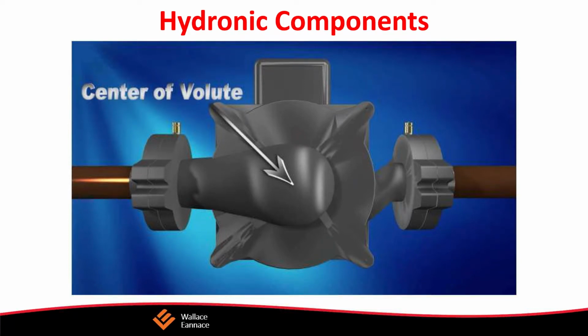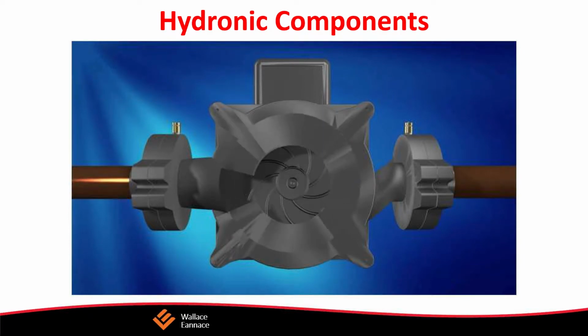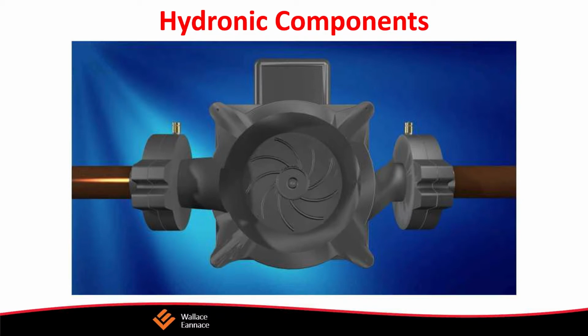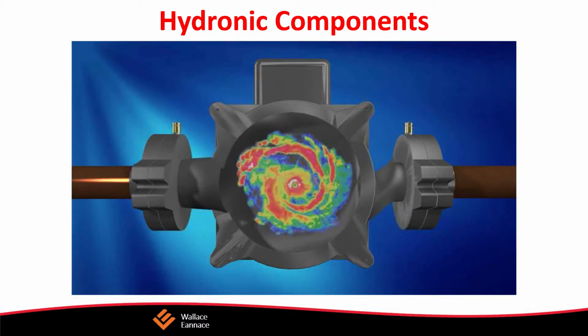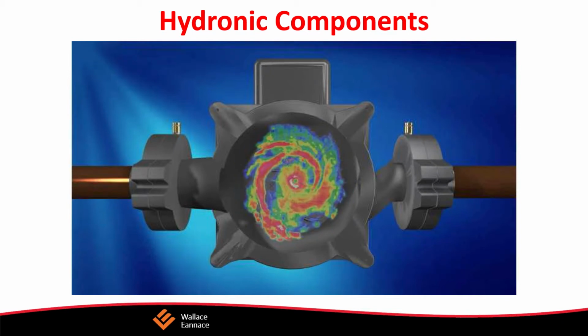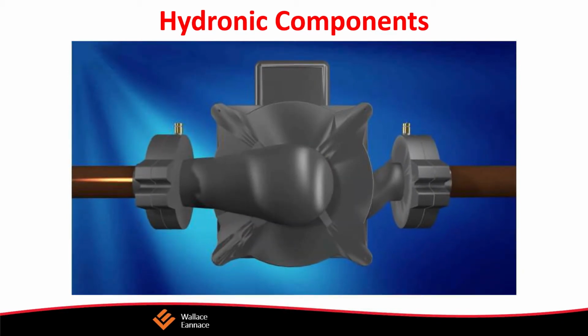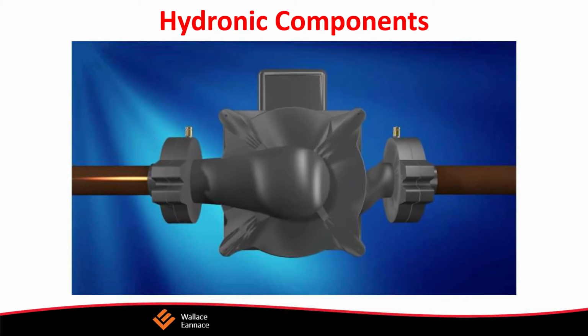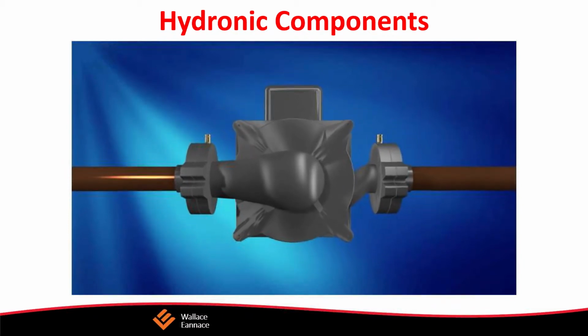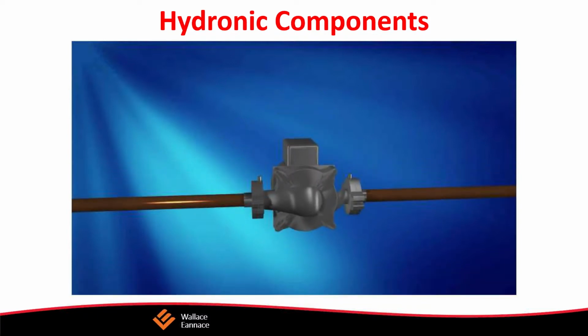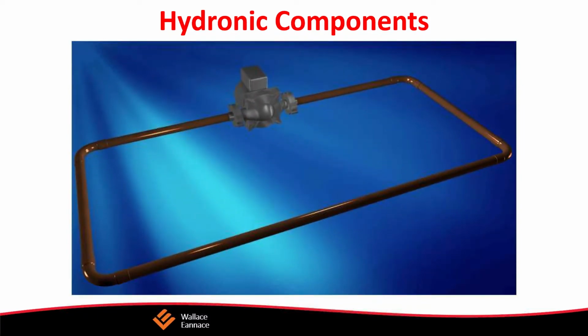So the first pump we're going to talk about is the most common pump that you see in a house and you see all over the place. Those are wet rotor pumps. The pump effectively moves water heated by the boiler around the system to and from the radiators, fan coils, baseboard, and radiant floors. Consider the pump flow rate as the train that heat travels on, and it's like the commuters on a train. They get on the train at the boiler and they hop off at the radiators like commuters would get off a train. The slower the water moves, the greater the delta T. The longer it's out there, the more heat gets off the train.